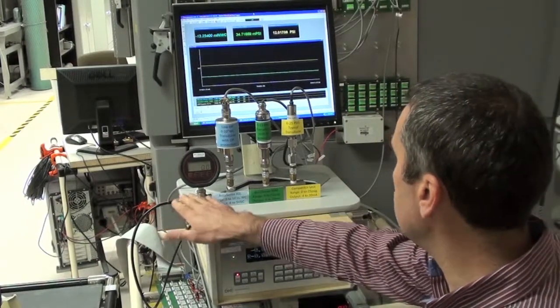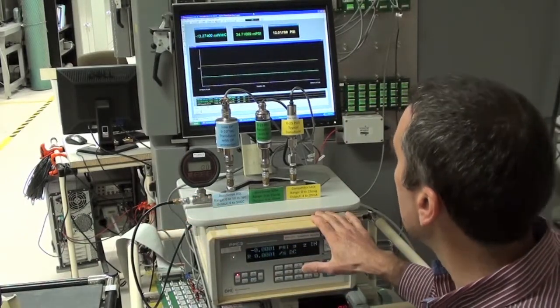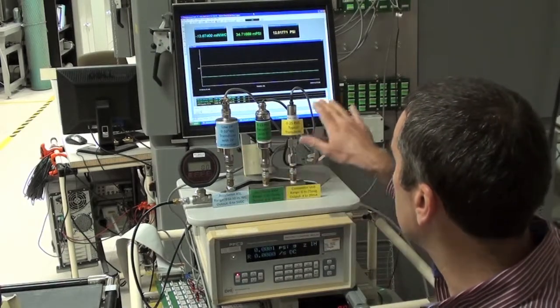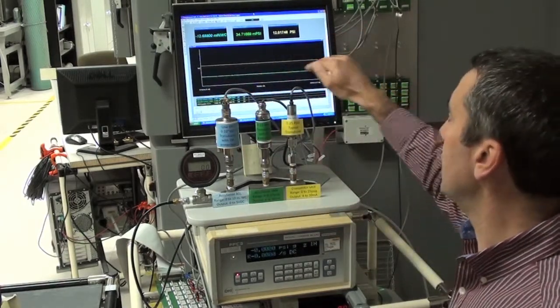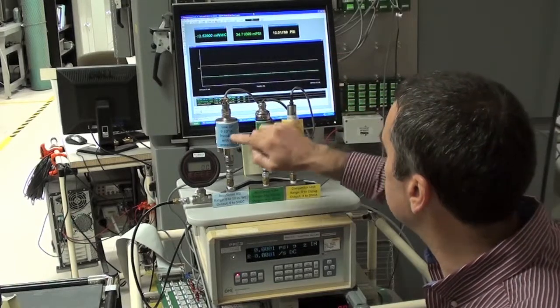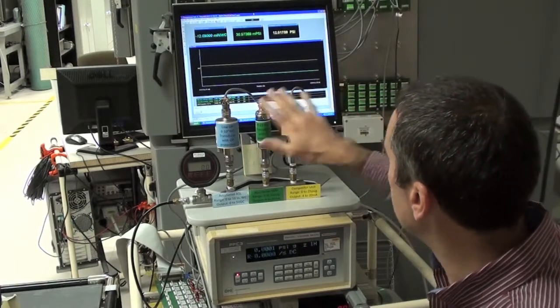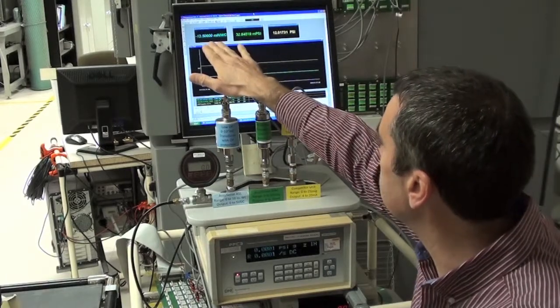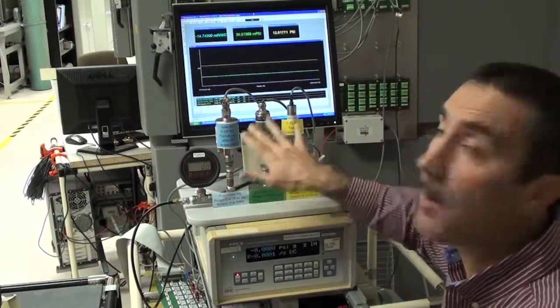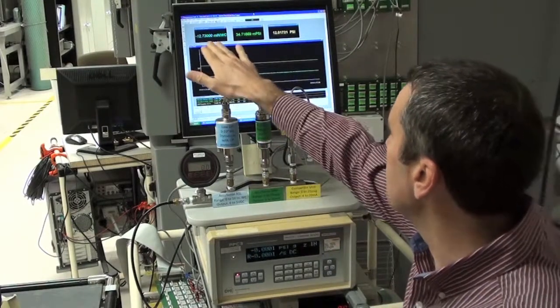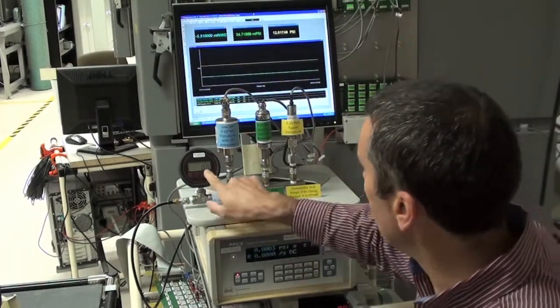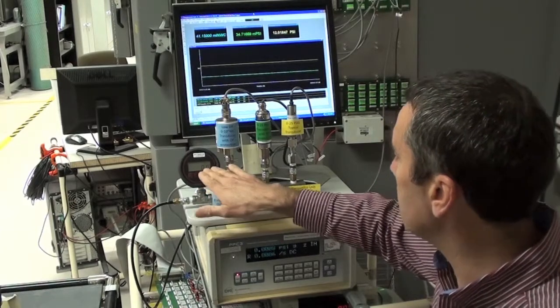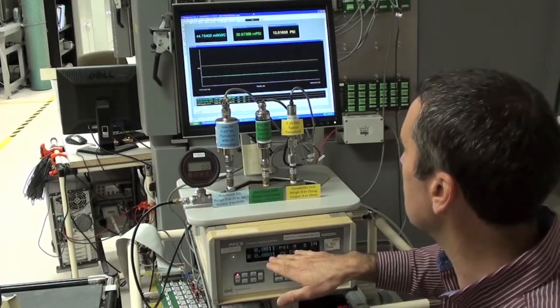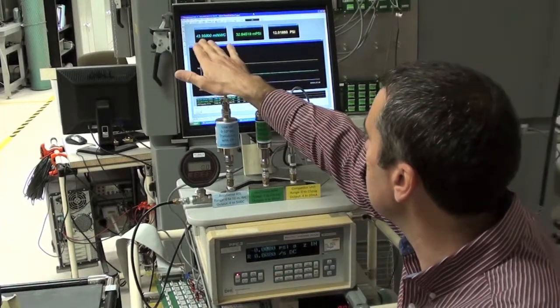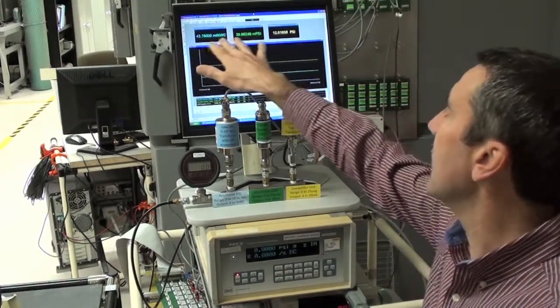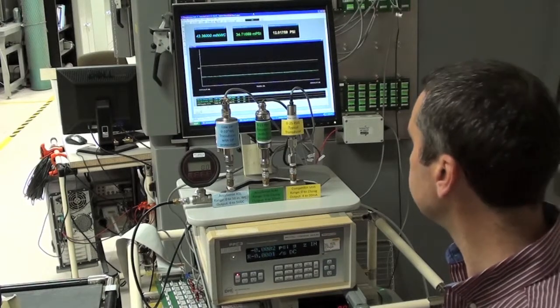So I have the manifold attached to a pressure controller, and the output of each transducer is being recorded on this strip chart. You can see there's the blue line, green line, and yellow line from these transducers, and there's a meter with a blue indication, green indication, and yellow corresponding to these transducers. These are reading very low values. We have 0. I have another digital gauge here showing 0 pressure. Control is having vented 0 pressure. You can see milli-inches of water, milli-psi, negligible pressure in the manifold right now.